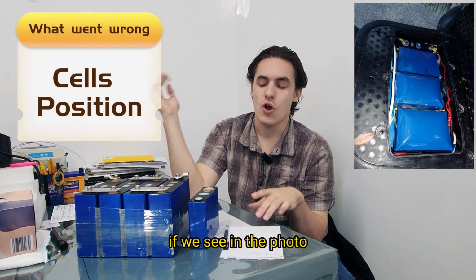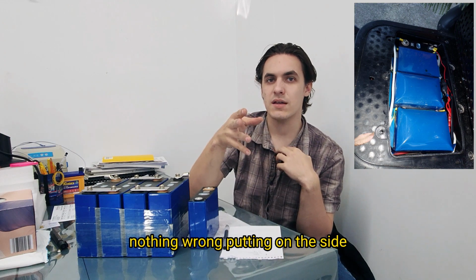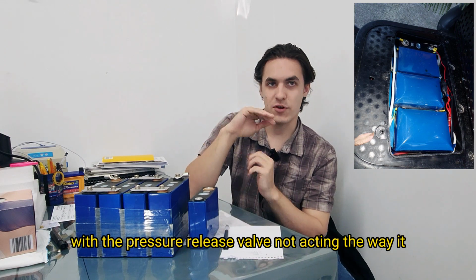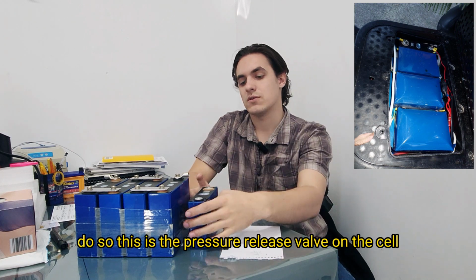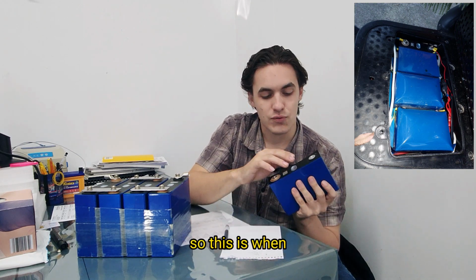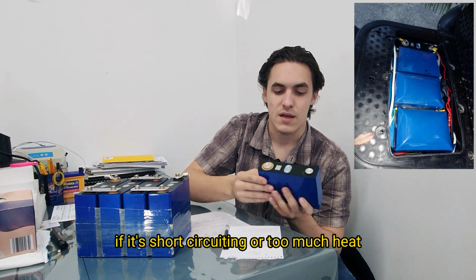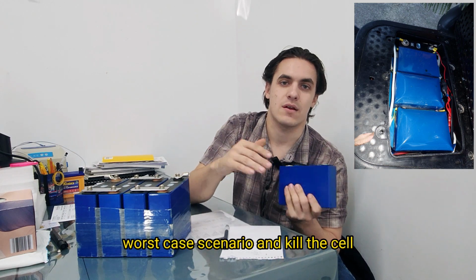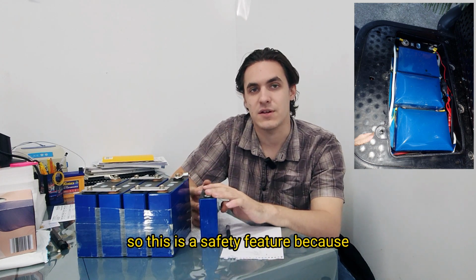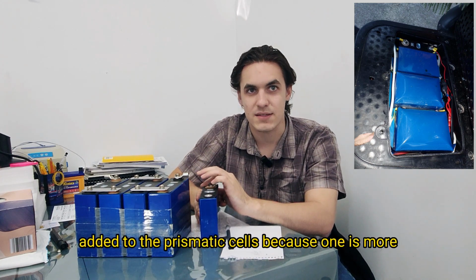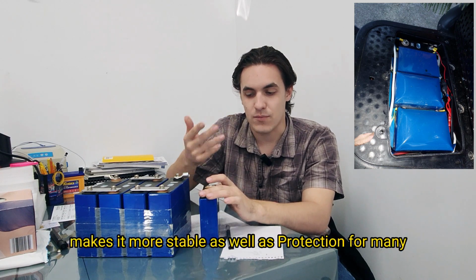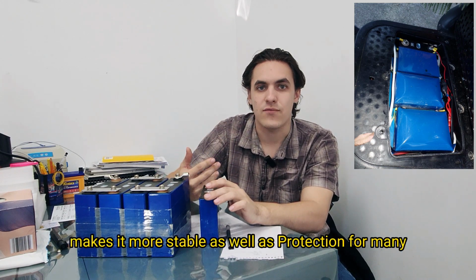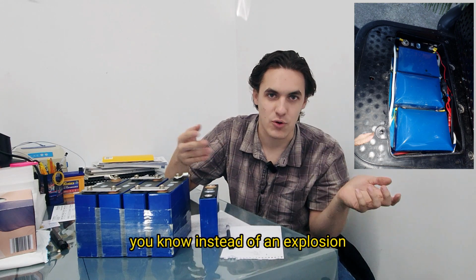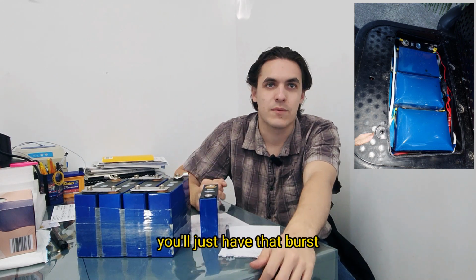Another thing is positioning. In the photo, we've got 3 cells on the side and 1 facing up. There's nothing particularly wrong with putting them on the side, but the issue arises with the pressure release valve not acting the way it should. This is the pressure release valve on the cell. If it's short circuiting or gets too much heat, it will burst that valve in a worst case scenario and kill the cell. This is a safety feature added to prismatic cells, making them more stable and protecting against an explosion, you'll just get that burst instead.